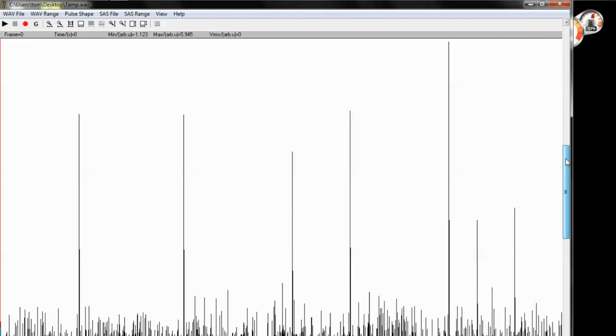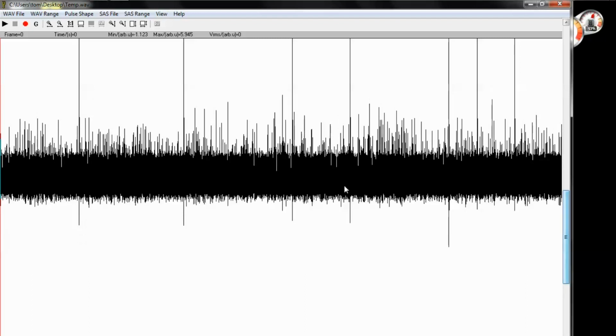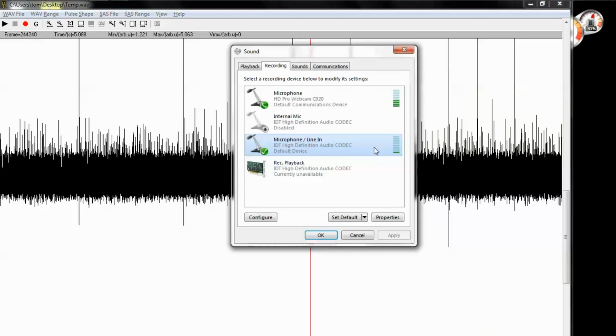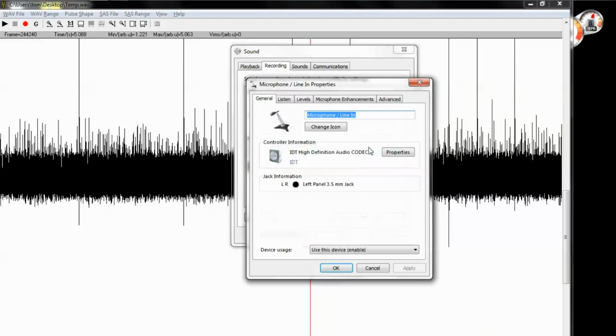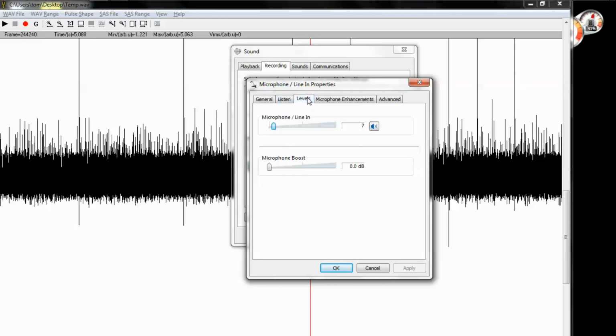As you can see, the arbitrary units you're looking at right now are between -1 and 5. So the maximum you're looking at here is 5 and 6. That's no good. You hit some of these high peaks right here that hit 30, still no good. This is too low. What you'd want to do is keep increasing the sound until you got it to where it was around 50 to 60. I'll go up to, let's say, 100. I like 100.